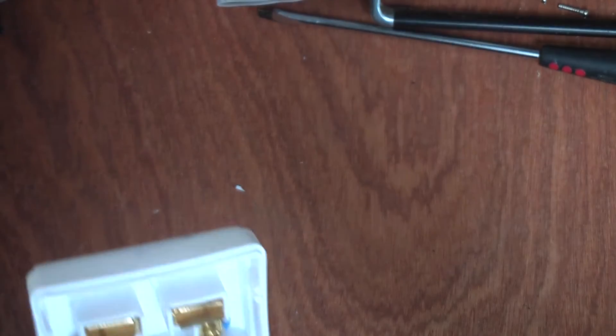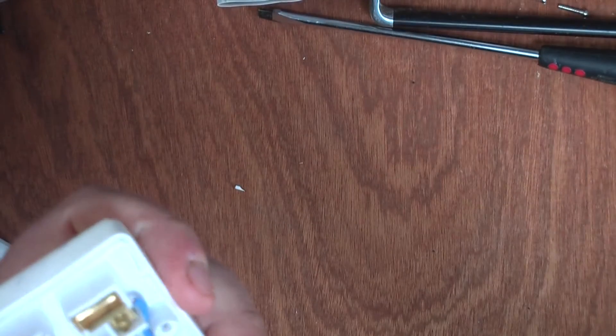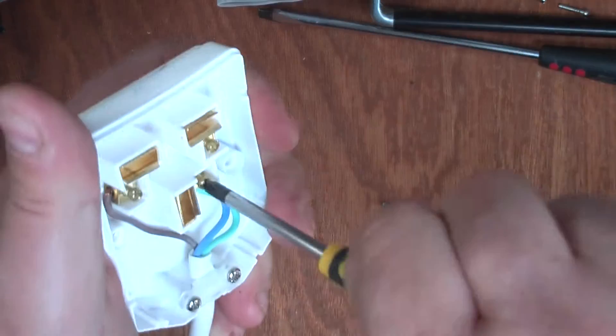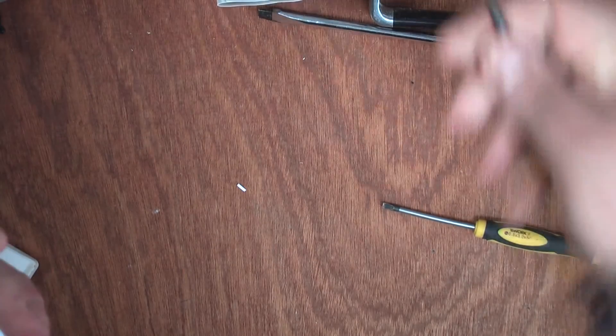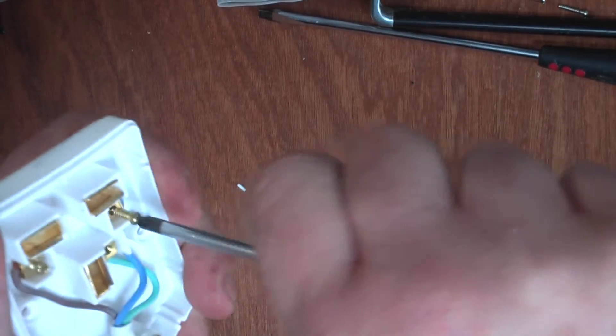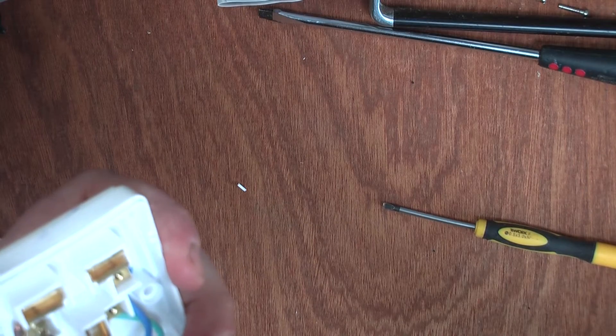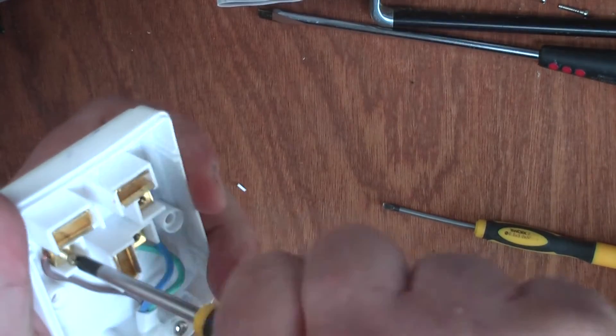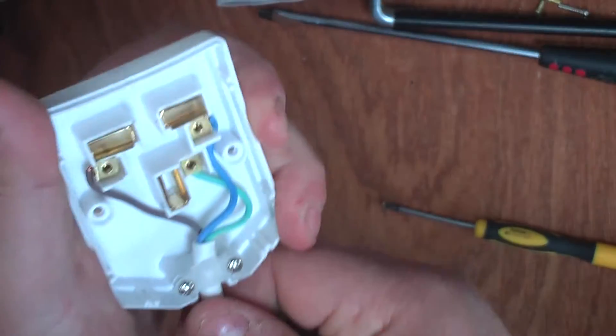Secondly, the length of the cord bothers me. Generally the live should be shorter than the neutral, and the neutral should be shorter than the earth, so that if anything pulls on it, the live gets pulled out first — and the earth will always remain connected to the end. Also, the cord strain relief isn't very good. The single cord-tensioning collar isn't providing as much strain relief as I'd like. Quality extension cords would have a rubber guide to prevent wear and tear where the cord enters the plug — this one doesn't.